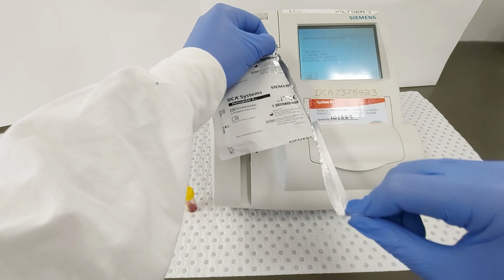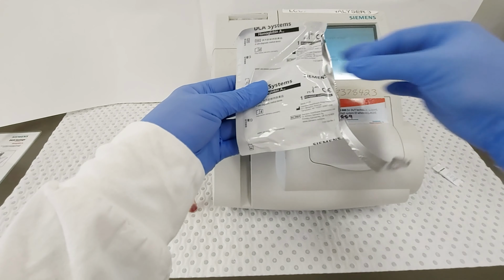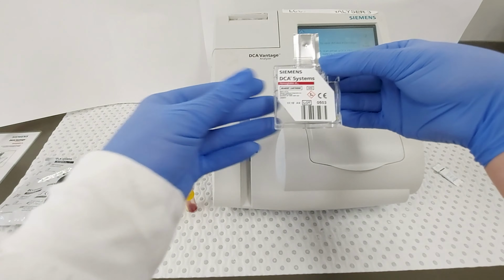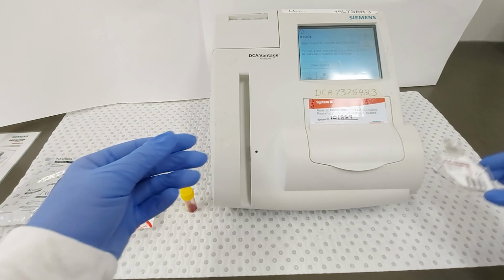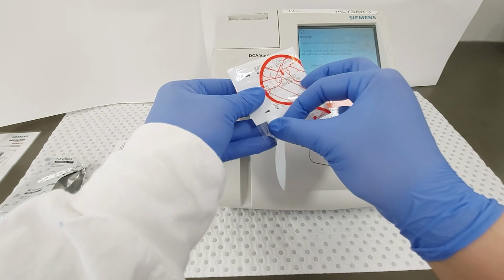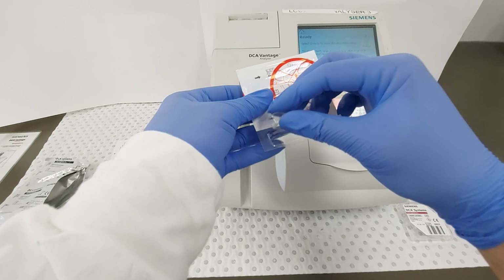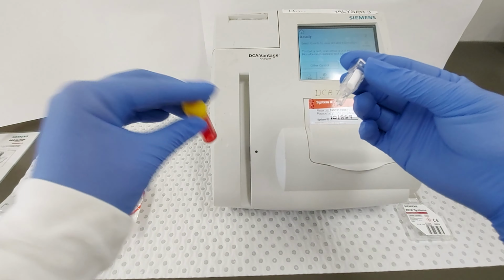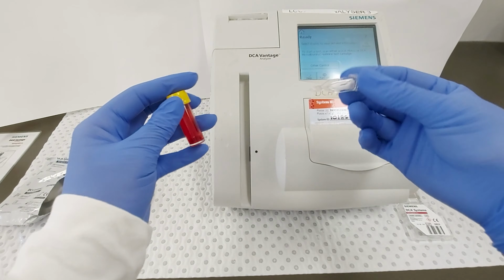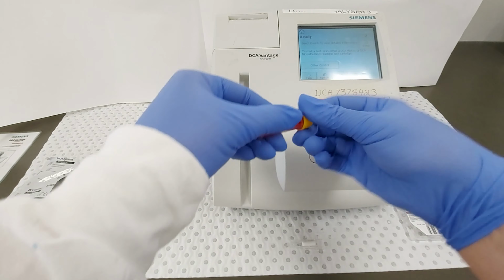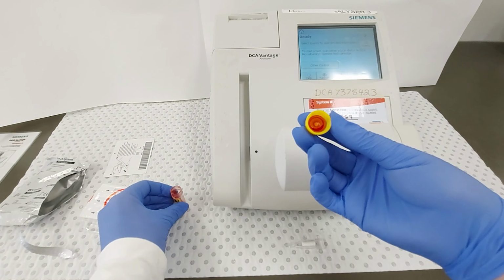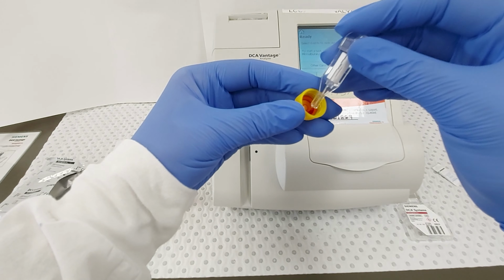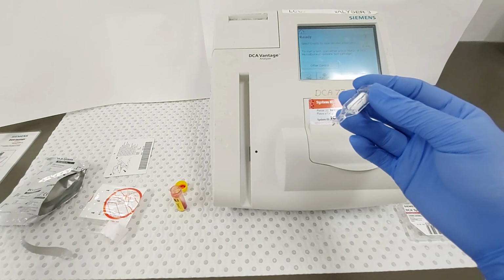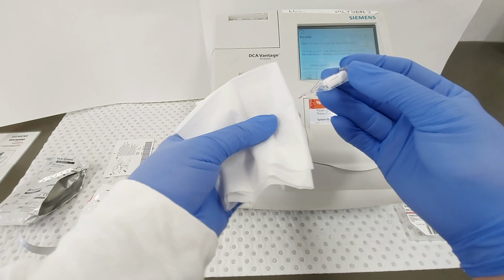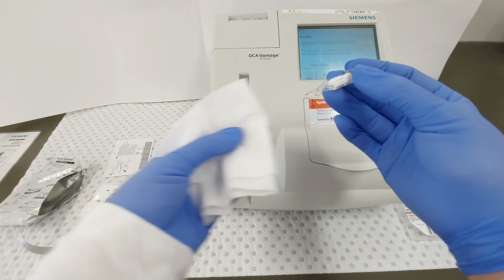Next, open the reagent cartridge package and set to one side. Open the sample capillary packaging by peeling the cover off, careful not to press on the middle of the capillary as it may snap. Use anticoagulated sample and invert multiple times before using the blood in the lid to fill the sample capillary. Use a tissue to wipe the outside of the capillary of excess blood.